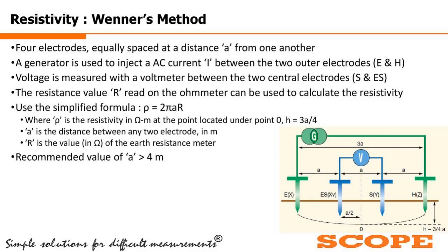Now h is generally 3/4 of A. There are 3 A's available, so this formula is also available on various platforms, even over the open net. There is a standard formula for how much depth the resistivity is measured at. So this is the depth, h equals 3/4 A, and A has to be constant between all the 4 poles or 4 electrodes. So we know the distance between any 2 electrodes, and the pi value is constant. The R value has been measured and displayed by the earth resistance measurement kit. So putting the standard value of pi, and as we know the distance A in meter, if we use the formula rho equals 2 pi AR, we will get the value of resistivity.